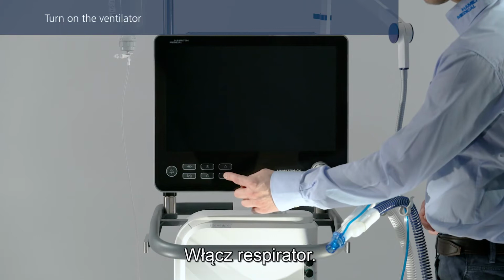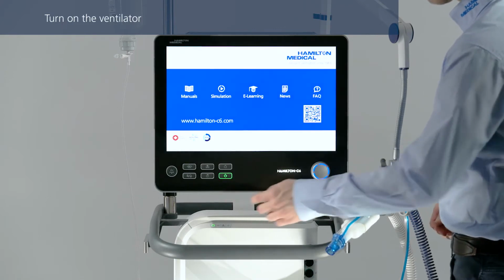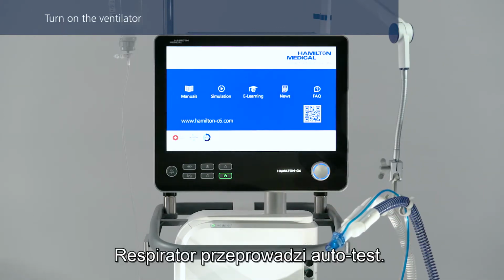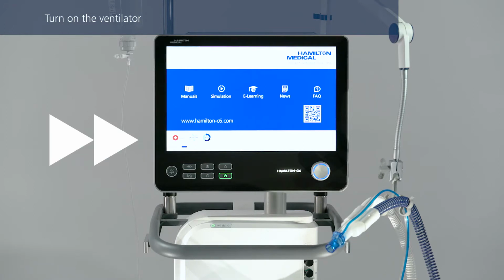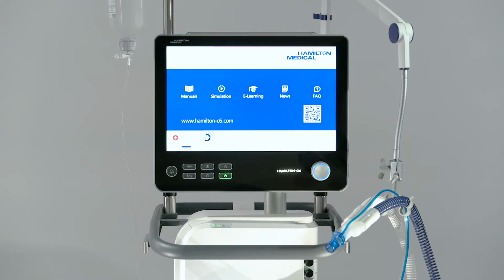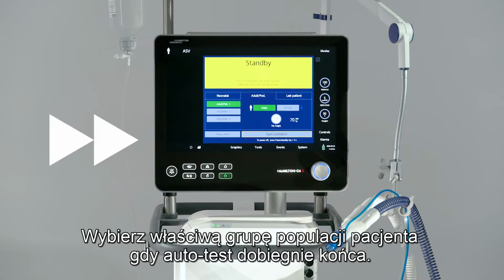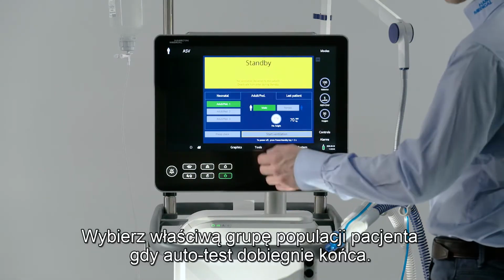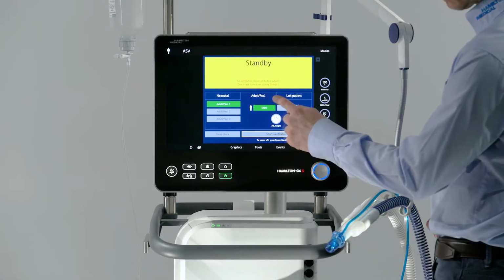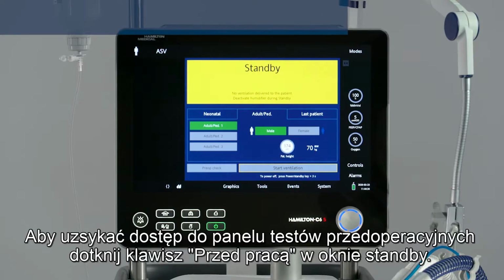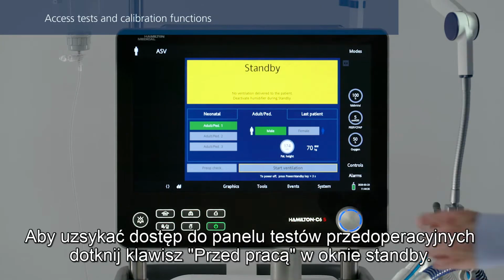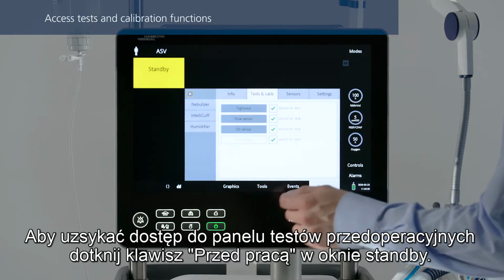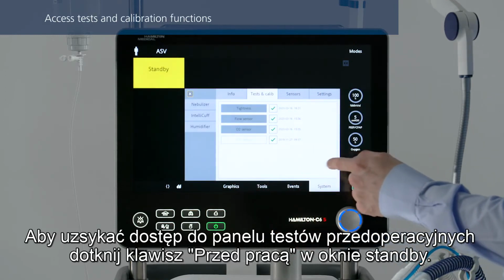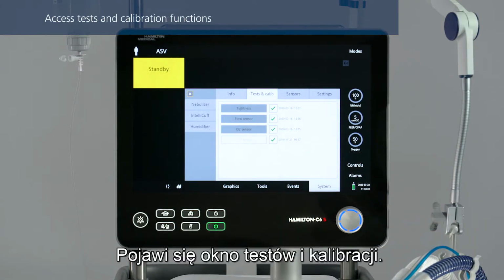Turn on the ventilator. The ventilator runs a self-test. When that is complete, select the correct patient group. To access tests and calibration functions, touch Pre-op Check in the standby window. The Tests and Calibration window opens.